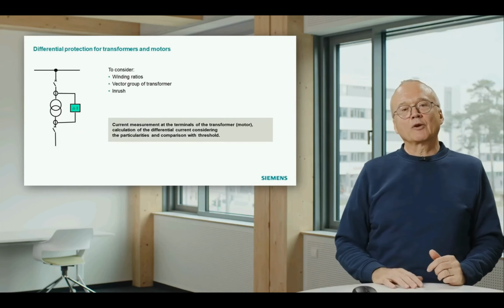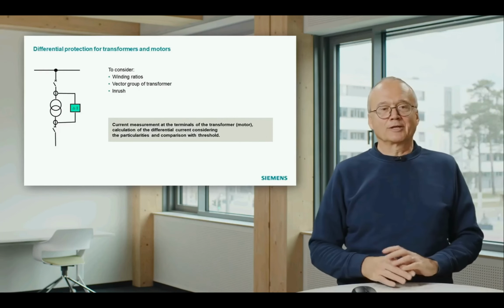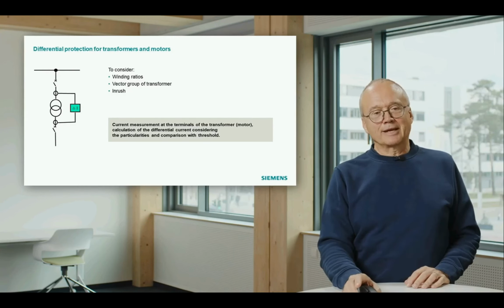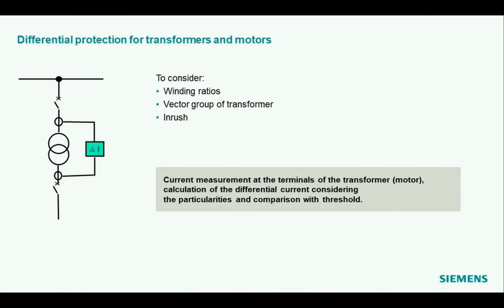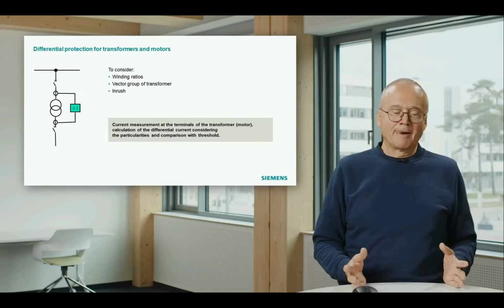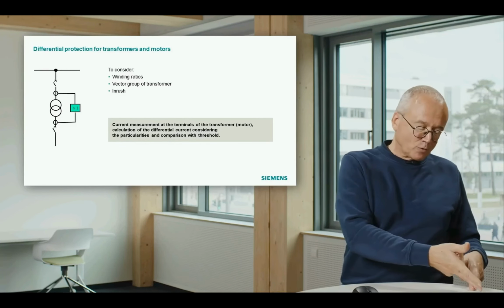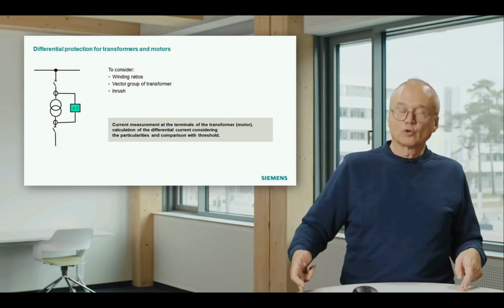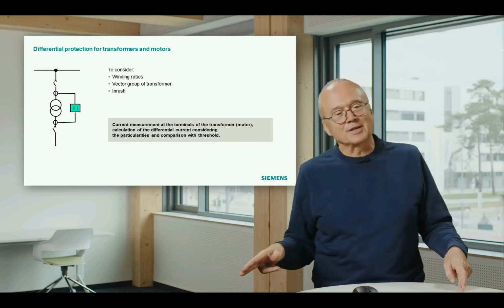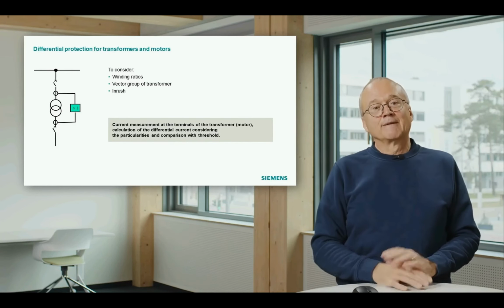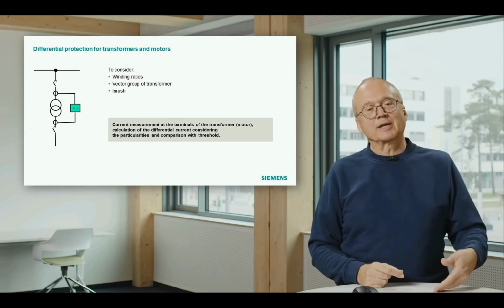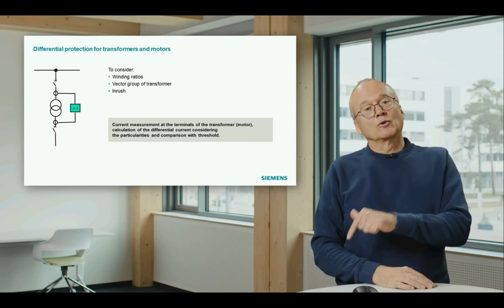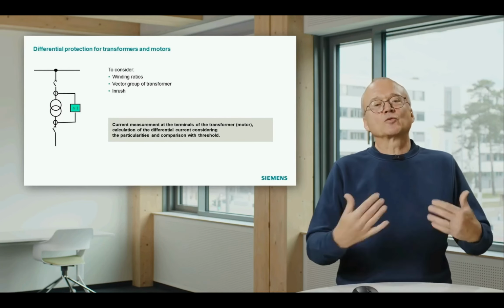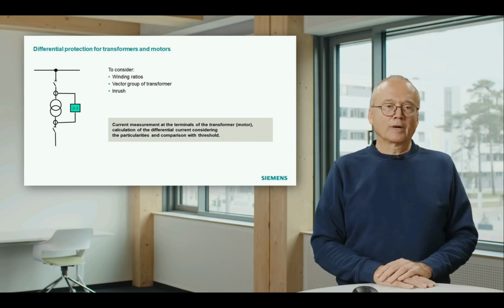The next area of application would be to apply that for a transformer. Then we don't need this communication thing because we are within one substation. We can measure the current on both ends of the transformer. But now we have to take into account a few other things, because on a line it's easy. If we have 100 amp flowing into the line, there should be 100 amp flowing out of the line on the other side. Of course, in a transformer, it's a bit different. Transformer has a winding ratio. That means if there is 100 amp flowing into the transformer, on the other side, we have a different current. That means we must take that into account to apply the winding ratio.